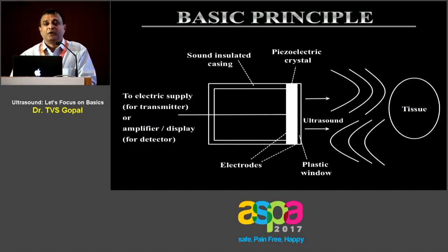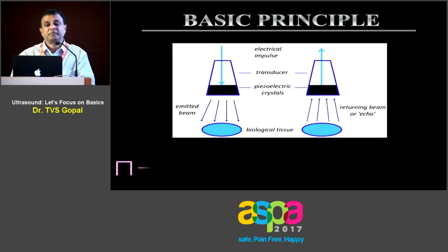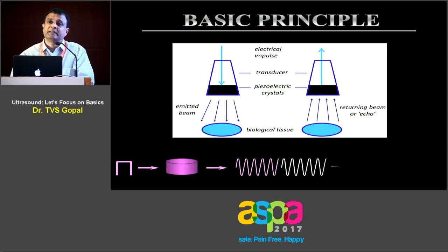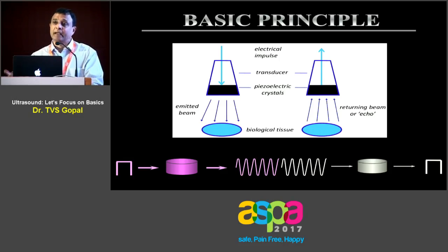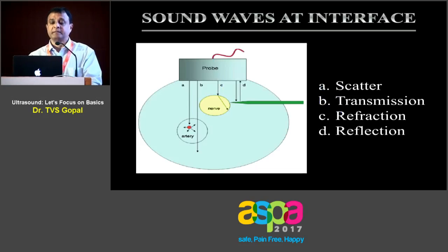This is the inside of a transducer or a probe, and the patient end of the transducer is lined by an array of piezoelectric crystals. When these crystals are stimulated by an electrical charge, they set off a wave, the ultrasound wave, which is propagated in the direction of the biological tissue that is to be imaged. A transducer, as we all know, is a device that converts energy from one form to the other. To begin with, electrical energy is converted into sound energy, and in the reverse direction, sound energy is converted again into electrical energy. So this is called the piezoelectric effect and the reverse piezoelectric effect.